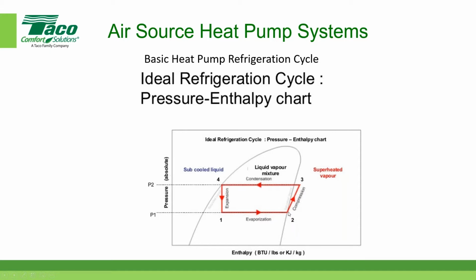So in terms of energy, you can see that the amount of energy that it takes to create the compression is relatively small. Let me kind of draw a vertical line here. Even though I don't have any values, you get the general idea here. Because the enthalpy lines in this case are vertical lines, there's the change in enthalpy due to the compression. And then if you look at how much energy can be rejected by the system, then the enthalpy difference is this whole value over here. So if I extended that line over there, you would see that the enthalpy is now this difference for the total amount of energy, and then this small distance over here for the compression energy or the work of the compressor.